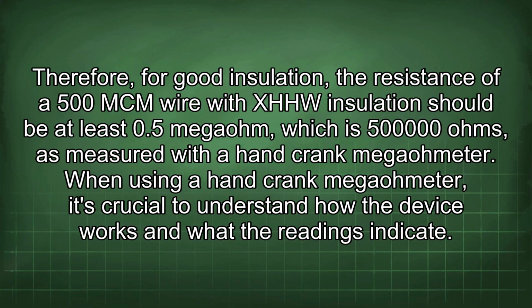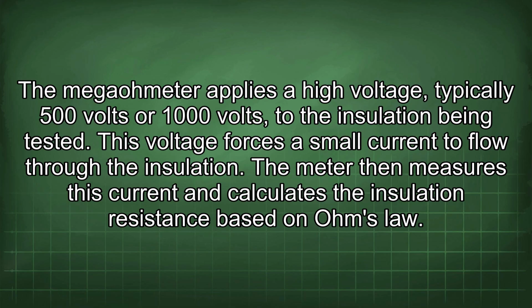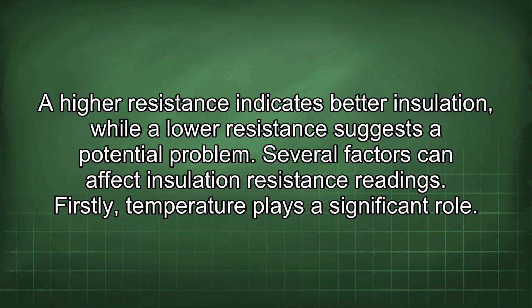Therefore, for good insulation, the resistance of a 500 MCM wire with XHHW insulation should be at least 0.5 megaohm, which is 500,000 ohms, as measured with a hand crank megaohmeter. When using a hand crank megaohmeter, it's crucial to understand how the device works and what the readings indicate. The megaohmeter applies a high voltage, typically 500 volts or 1000 volts, to the insulation being tested. This voltage forces a small current to flow through the insulation. The meter then measures this current and calculates the insulation resistance based on Ohm's law. A higher resistance indicates better insulation, while a lower resistance suggests a potential problem.